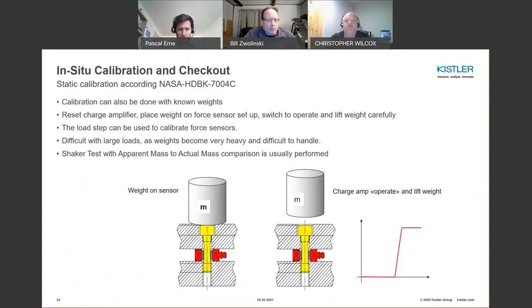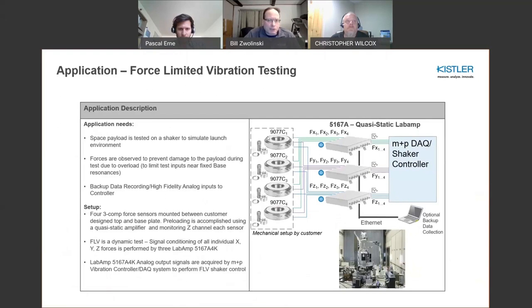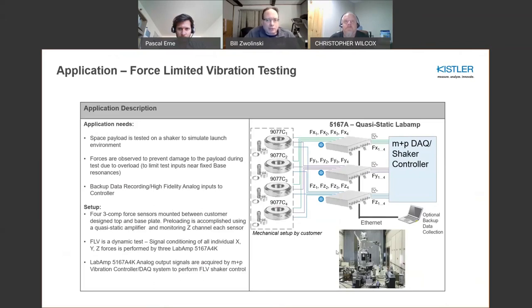In-situ calibration using force sensors might make sense for small installations, but for large platforms the shaker-based apparent mass versus actual mass comparison is the preferred industry approach. The final force limited test setup shows four sensors going to the lab amps — the 5167 quasi-static units — which are used both for preload and for dynamic measurement. Each lab amp has four outputs, so all 12 channels are routed directly to the M+P shaker controller system, giving complete visibility of all channels. With everything preloaded and calibrated, you are ready to test.